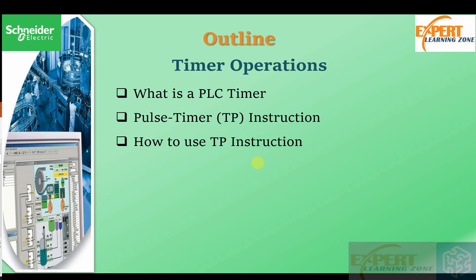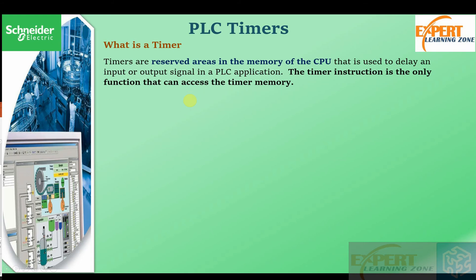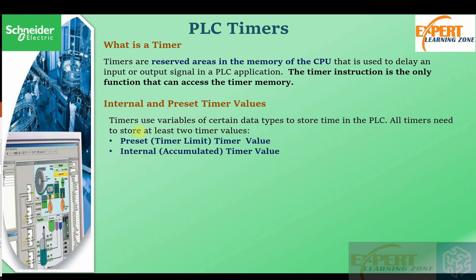First, what is a timer? Timers are reserved areas in the memory of the CPU that are used to delay an input or output signal in a PLC application. A timer instruction is the only function that can access the timer memory. Timers generally have two values: the internal timer value and the preset timer value.